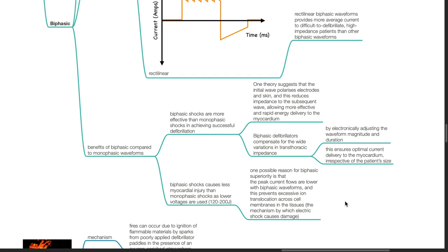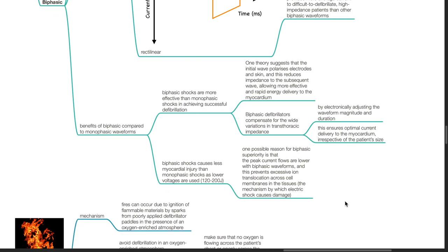Benefits of biphasic compared to monophasic waveforms: biphasic shocks are more effective in achieving successful defibrillation. One theory suggests the initial wave polarizes electrodes and skin, reducing impedance to the subsequent wave and allowing more effective energy delivery to the myocardium. Biphasic defibrillators compensate for wide variations in transthoracic impedance by electronically adjusting waveform magnitude and duration, ensuring optimal current delivery irrespective of patient size. Biphasic shocks also cause less myocardial injury, using lower voltages of 120 to 200 joules, as lower peak current flows prevent excessive ion translocation across cell membranes.